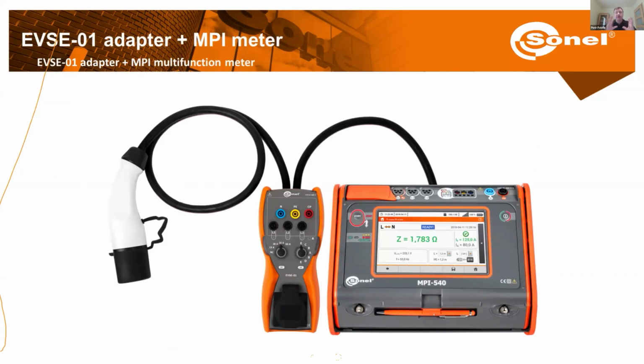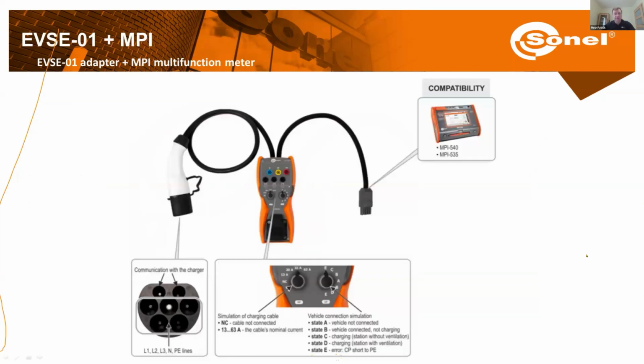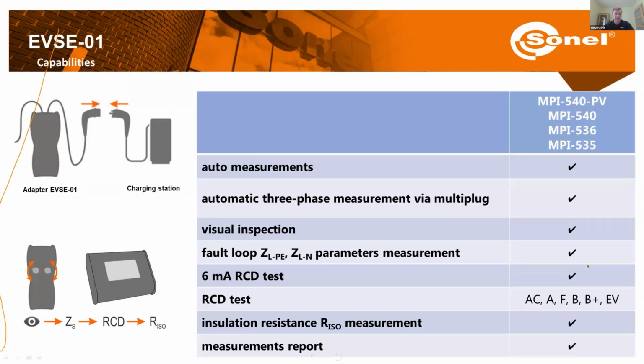Now, another solution is using a multifunction meter together with the EVSE01 adapter. So here, the adapter is just the interface between the meter and the charging station. On one end, it has a multi-plug, which we can connect into the meter. On the other end, it has a Type 2 connector. And again, the adapter allows us to simulate different states and different currents up to 63 amps. So that's for control pilot and proximity pilot. And it can perform different measurements: fault loop impedance, RCD parameters of different types of RCDs, insulation resistance, continuity, phase rotation, and we can create an automatic sequence of measurements. So then we don't need to go to a different measurement function. Once we set up this sequence, the meter will just go through all the designed measurements.